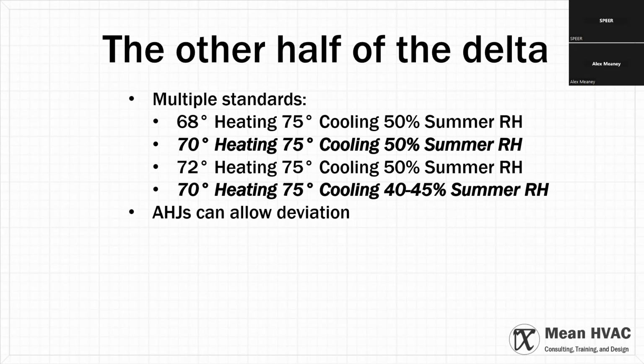For what it's worth, when I'm teaching classes in humid climates, I strongly recommend that they never drop below 72 as a design standard, simply because there's a lot of manufacturers where they're, like places like Houston, I would tell them not to at all. But 70 to 72, I would never allow anything below 70. Below 70, I can't get any manufacturer data on the performance of the system. And I would question using 70 pretty much for reasons of standard comfort.